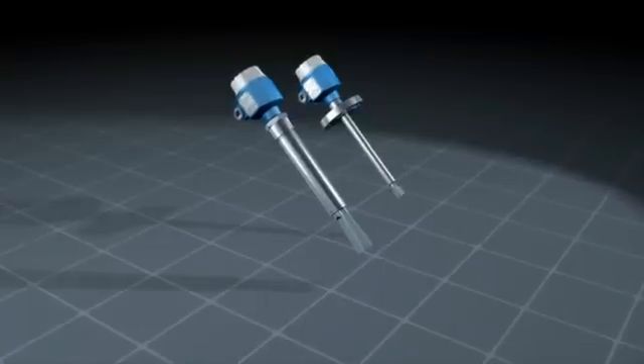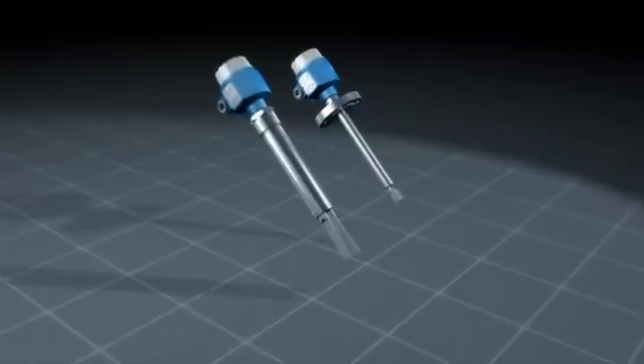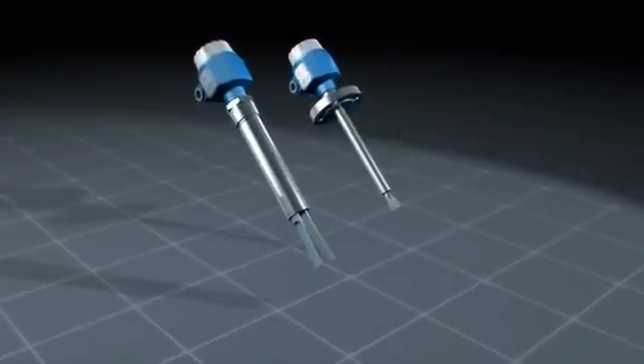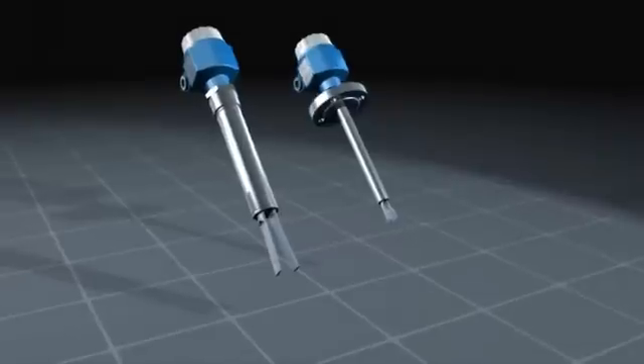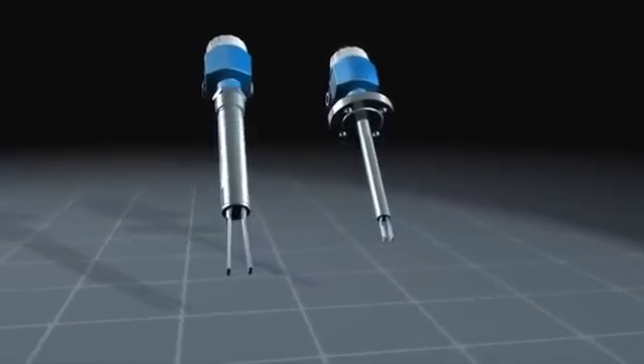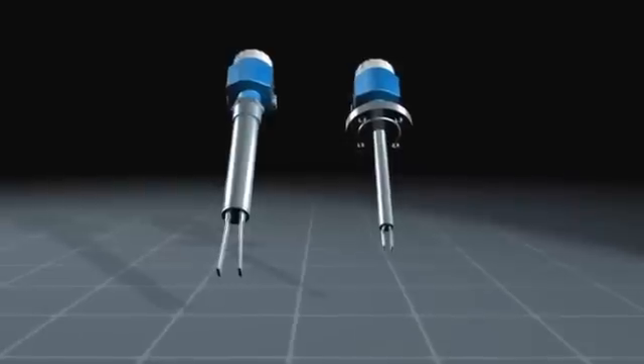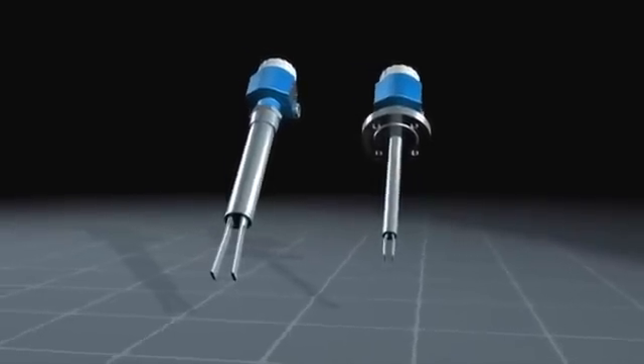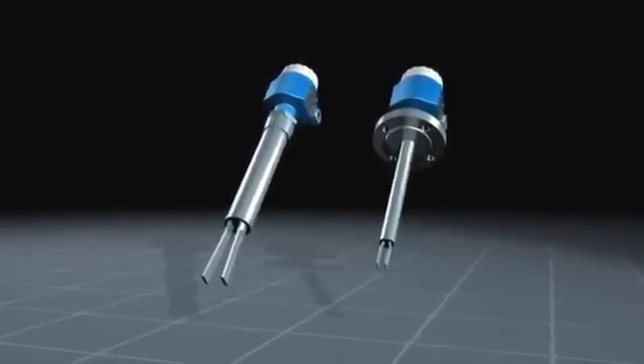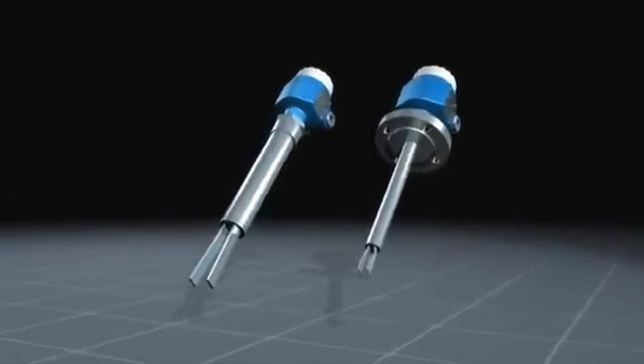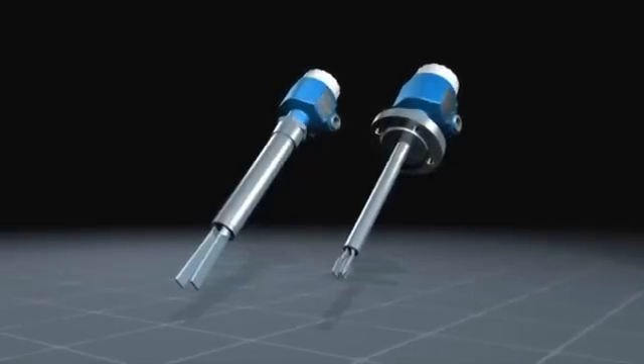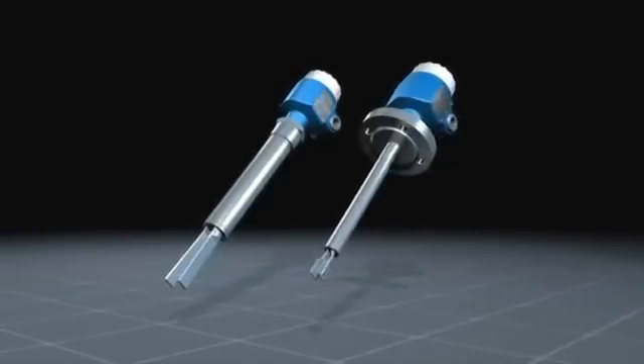The vibronic measuring principle of Endress+Hauser enables point level detection unaffected by the physical properties of the medium. For example, conductivity, dielectric constant, density changes, pressure, or temperature. Turbulences, the formation of foam, or bubbling liquids do not impair the point level detection either.